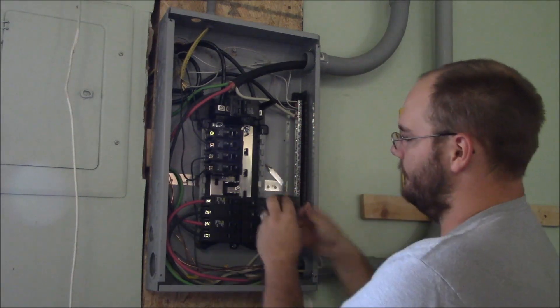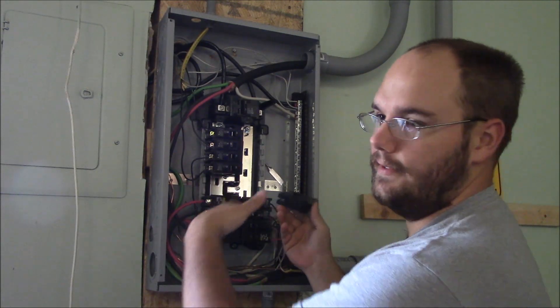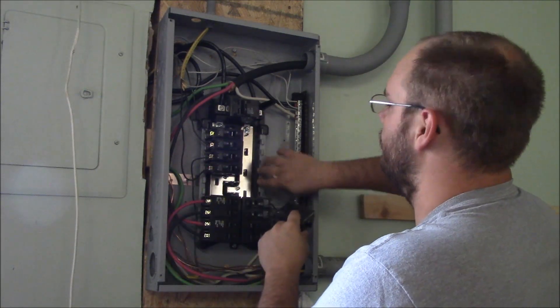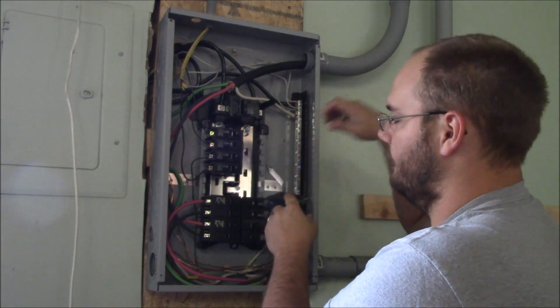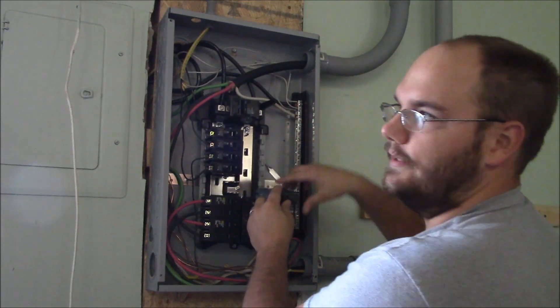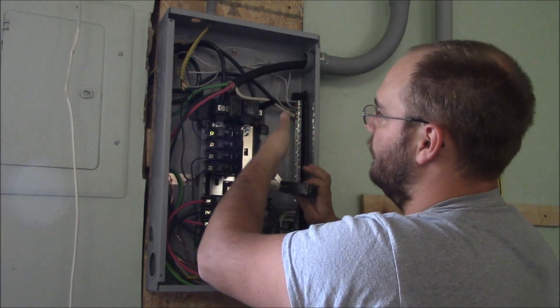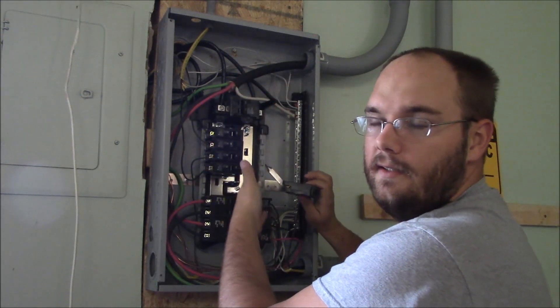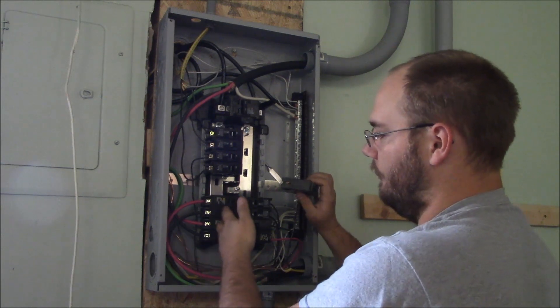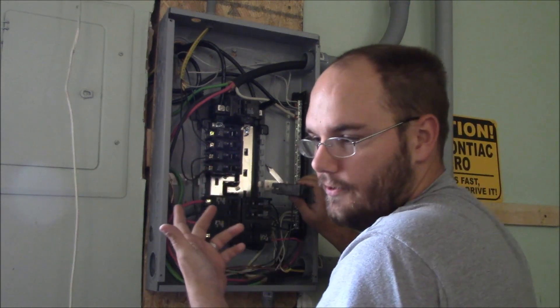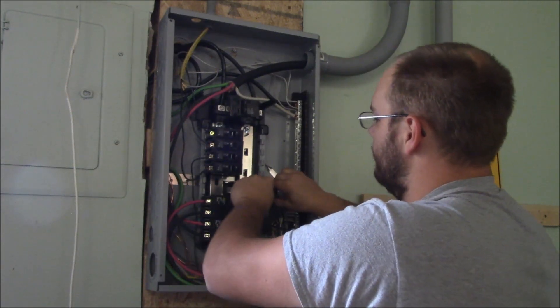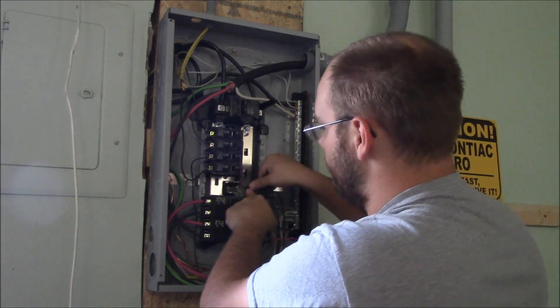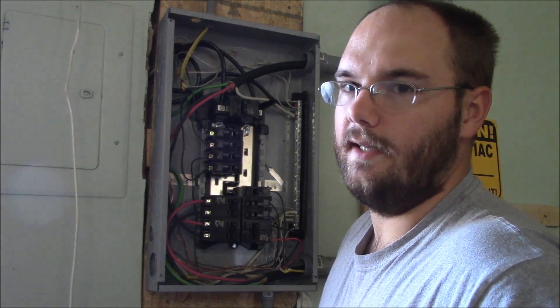And with this type of breaker, it's different depending on the type of box and the bars that you get. With this one, you've got this bar here which is completely dead, and then you've got your—I don't know what the term is—your tree. It's your hot, you got both poles coming in, so one is 110, the next one's 110. And the reason why you get 220 is you'll have a larger one that will go over and grab one from each, and that gets you your 220. So on this one, it's got this clip in there that you push there, and then you just push this down onto the tree, and that's that.